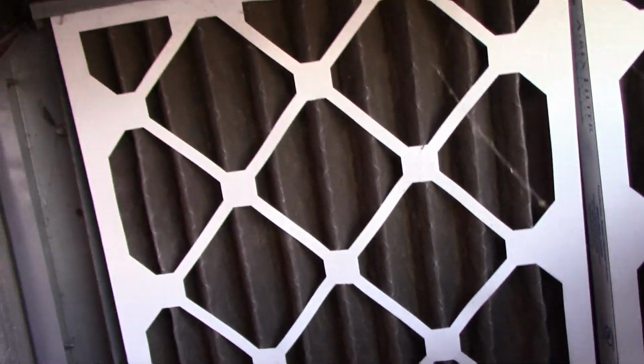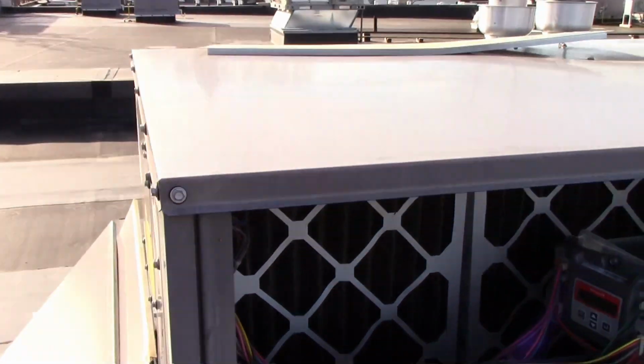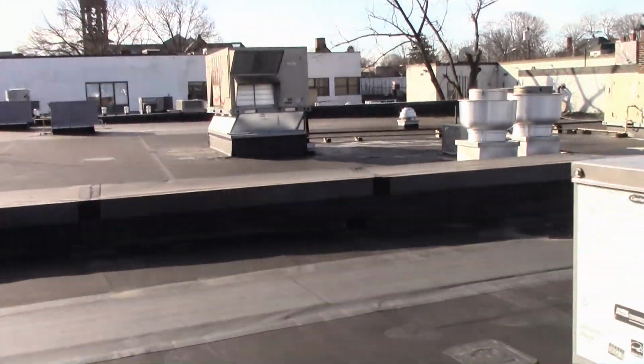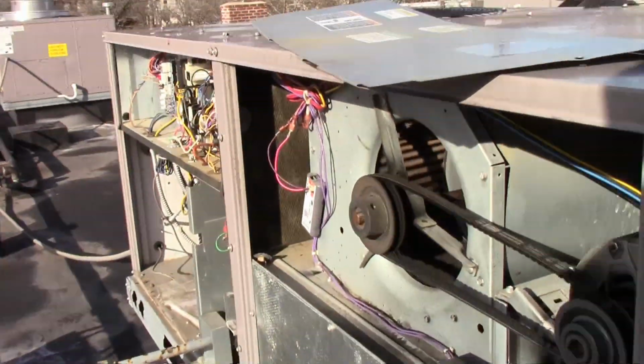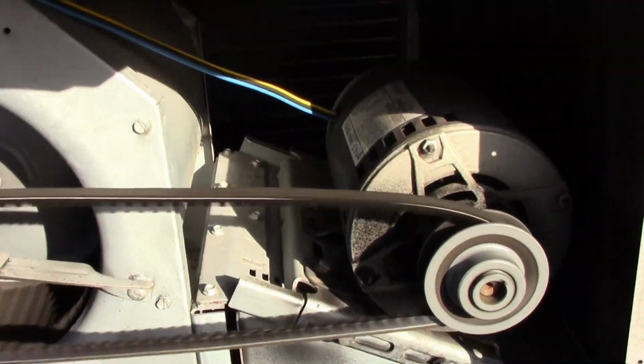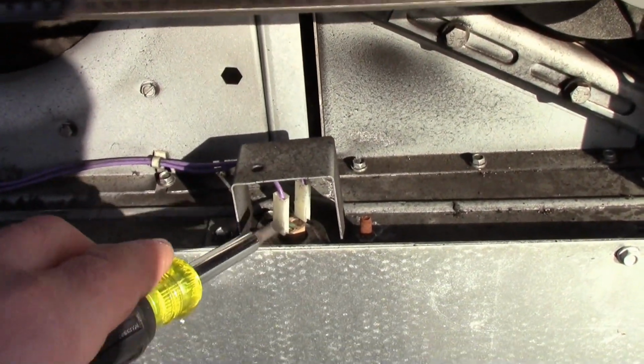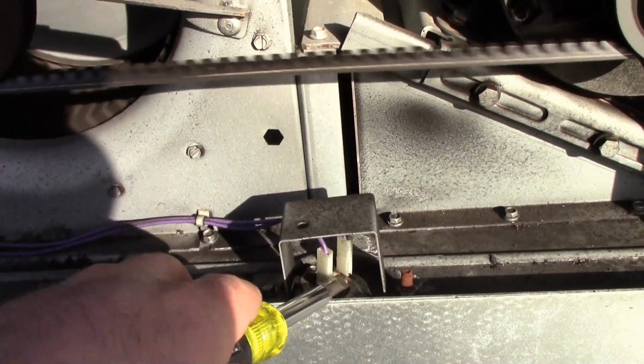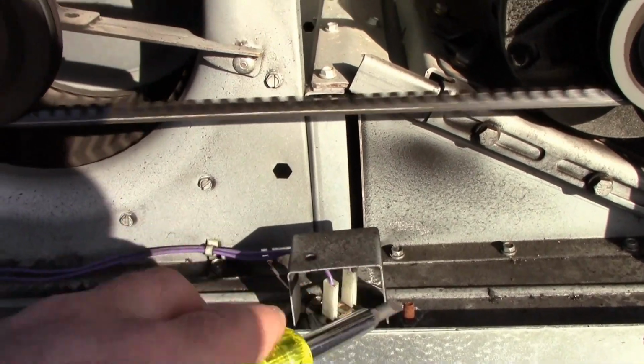Filters look absolutely horrible, so those are going to get pulled. So we do have a low airflow condition. That's more than likely our problem, but our limit switch is right here, and I'm going to take my meter and go across it real quick and see if it's closed or open.